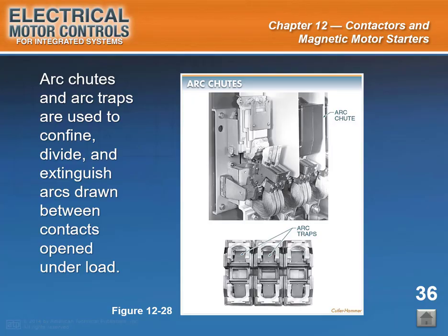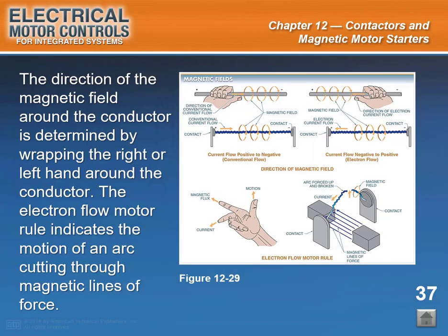Slide caption: arc chutes and arc traps are used to confine, divide, and extinguish arcs drawn between contacts opened under load. See Figure 12-28. An arc chute is a device that confines, divides, and extinguishes arcs drawn between contacts opened under load. Arc chutes are used to contain large arcs and the ionized gases created by them. Arc chutes employ the de-ion principle, which confines, divides, and extinguishes the arc for each set of contacts. End of slide 36. Start of slide 37.